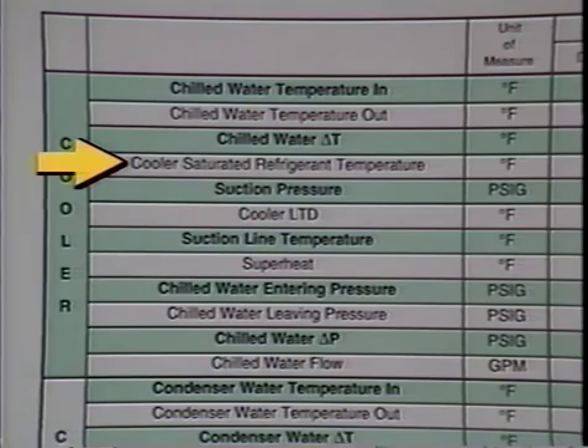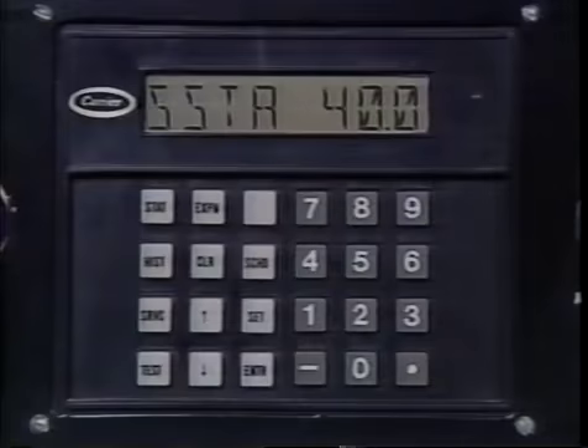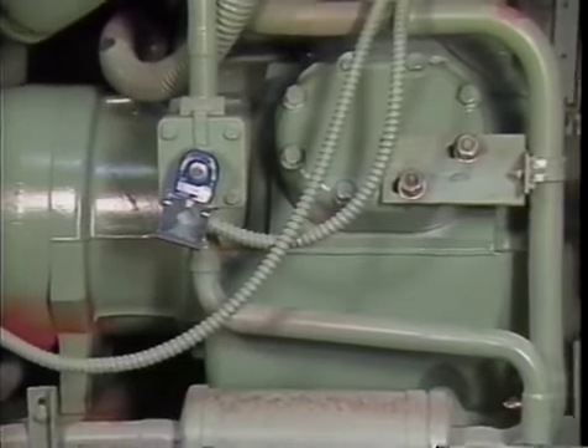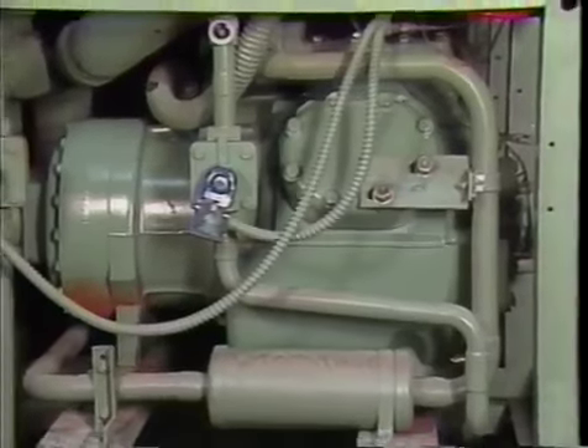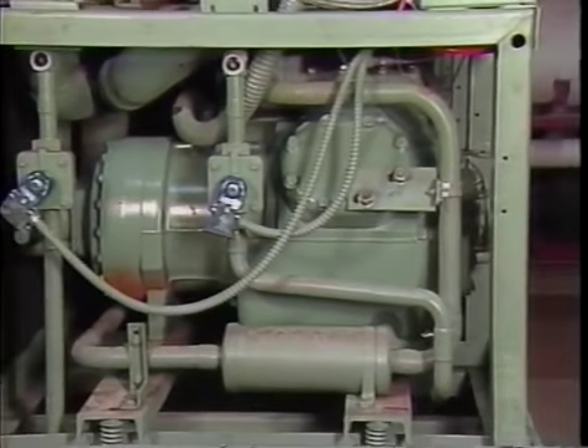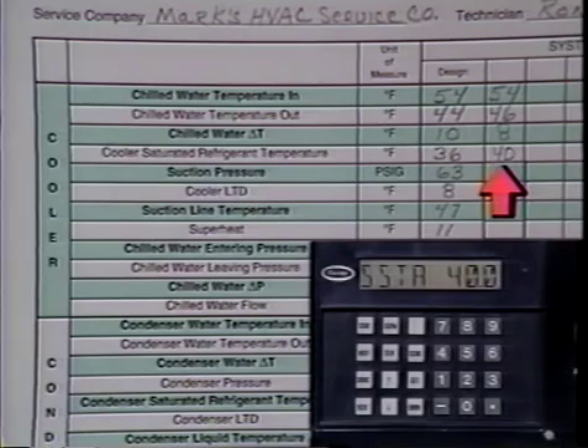Cooler saturated refrigerant temperature. A space is provided to record the cooler saturated refrigerant temperature. Under maximum heat load conditions with the machine operating at design, this temperature should be at the design temperature. Under reduced heat load operation, when the compressor is running unloaded, this temperature will be above design. Under no circumstances, even at full load operation, should this temperature be allowed to drop below the design temperature, which is typically a few degrees above 32 degrees Fahrenheit.